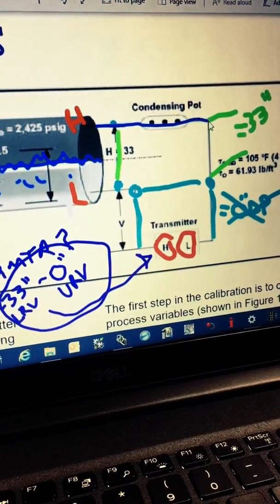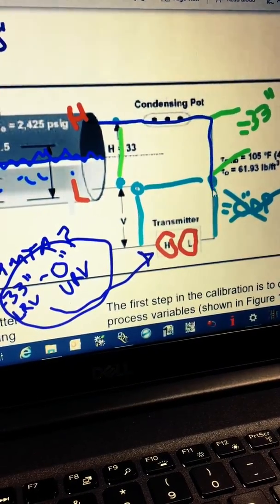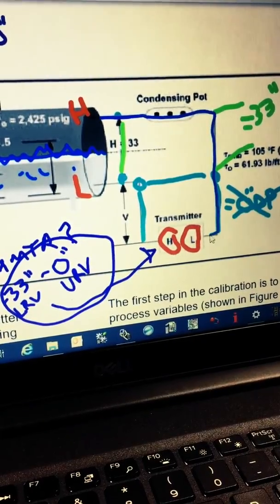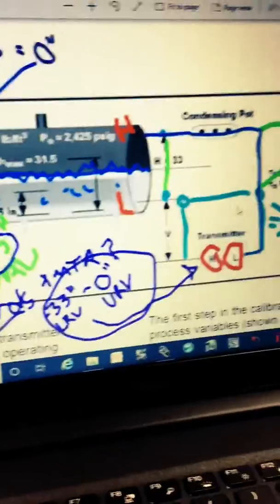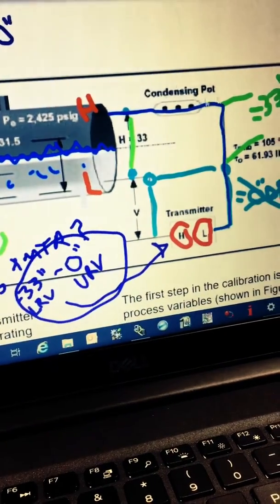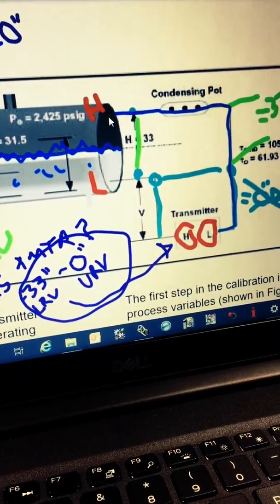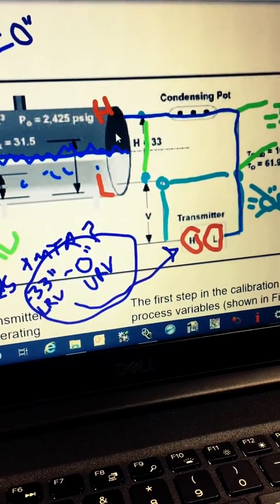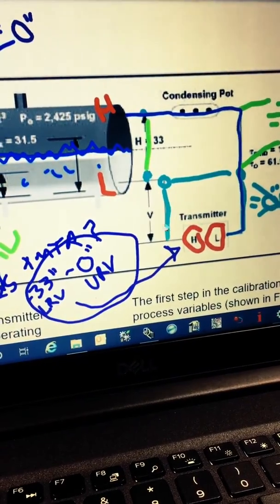So, you see we come through this condensing pot. And we have the reference leg here. And you always want to make sure that that reference leg is full of water before you ever fire up the boiler. Otherwise, you're going to have a really hard time controlling the drum level. So, fill up that reference leg.